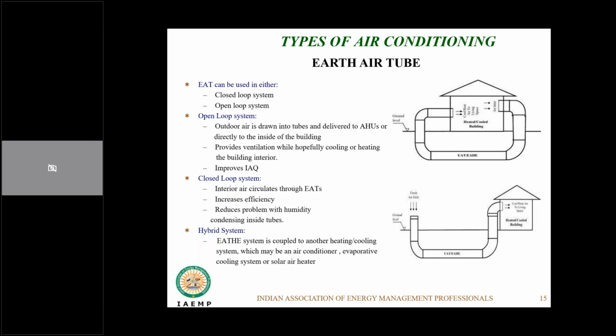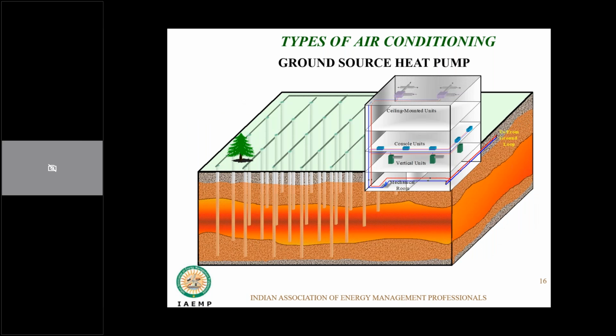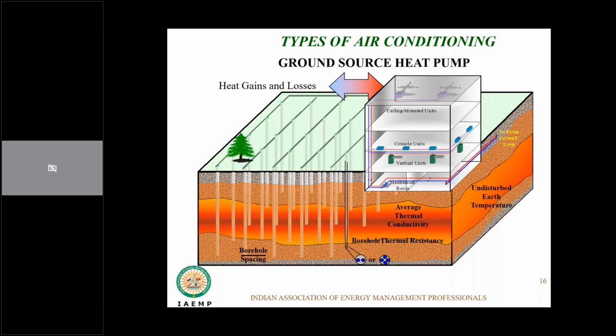So you can add a cooling coil further to it to treat it further and take the temperature down. Also, a heat pump is a similar application, but it doesn't directly cool the air; it becomes a source of your heat rejection. Normally you have a cooling tower for heat rejection, or you have an air cooled system for the heat rejection. In a ground source heat pump, you have bore wells where you bury the pipes, and the heat of condensation, which you normally use for any vapor compression system, is transferred over here. So you don't need any water or anything for heat rejection.